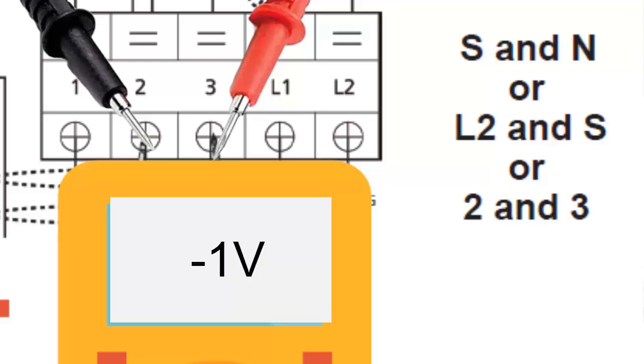7. On the other hand, if the indoor unit has a fault, the previously measured voltage will remain at a fixed value. 8. If the outdoor unit has a failure, the previously measured voltage will always remain at a positive value.